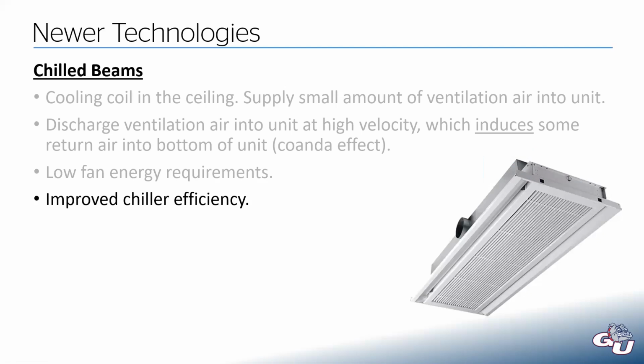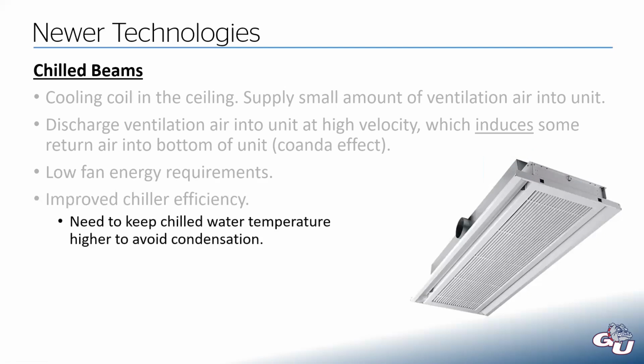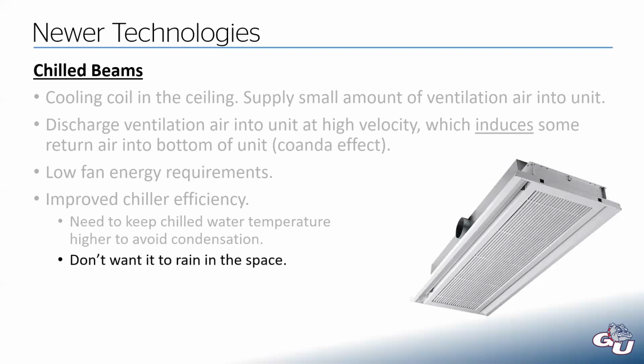The reason being, with chilled beams, you need to keep your chilled water temperature higher. A typical chilled water system supplies water at right around 45 degrees Fahrenheit. The problem is, if you put 45 degree water through this coil, you're going to have that latent load. You're going to be below the dew point of the air that it's pulling in, and you're going to cause it to rain in that space. Remember that every cooling process, or most cooling processes, they produce condensate. They produce water because it's sweating it out of the air. And we don't want that to happen here.